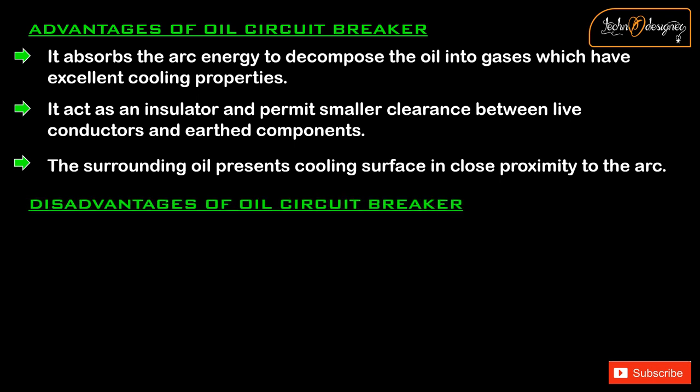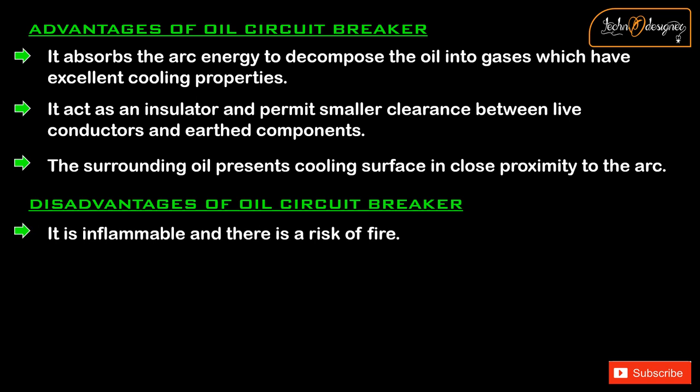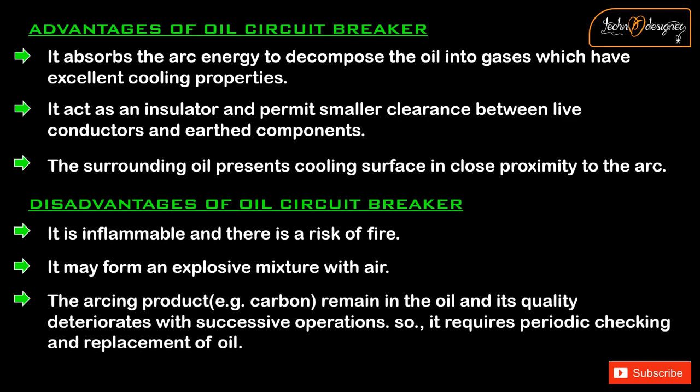Disadvantages of oil circuit breaker: It is inflammable and there is a risk of fire. It may form an explosive mixture with air. The arcing products, for example carbon, remain in the oil and its quality deteriorates with successive operations, so it requires periodic checking and replacement of oil.